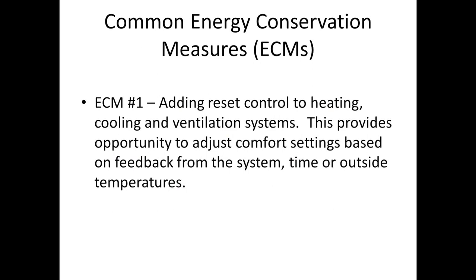Looking at things like outside air temperature, pressure differential, return either hot water or chill water temperatures or air temperatures. We can reset a system, so it's actually looking at and obtaining feedback from different parameters within the building and adjusting supply settings based on that.